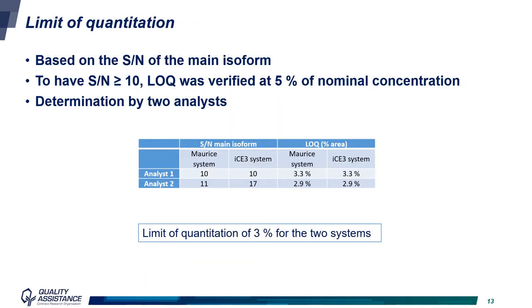The other main parameter evaluated was the limit of quantitation. This determination was based on the signal-to-noise ratio of the main isoform. To have a signal-to-noise ratio above 10, LOQ was verified at 5% of the nominal concentration, which is 0.015 mg/mL. This was checked on independent runs on both systems by two analysts, and in all cases, a limit of quantitation of 3% was found, indicating equivalent LOQ for both systems.